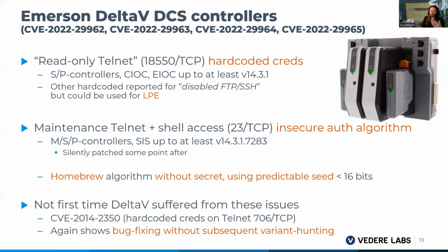But on top of that, there's no secret being used. There's no secret key, nothing negotiated. Instead, it relies on a predictable seed smaller than 16 bits. So as soon as an attacker reverse engineers this mechanism, they can reproduce it and get shell access to these controllers, which is even worse than being able to download a malicious strategy to it, because you have very low level access at that point.